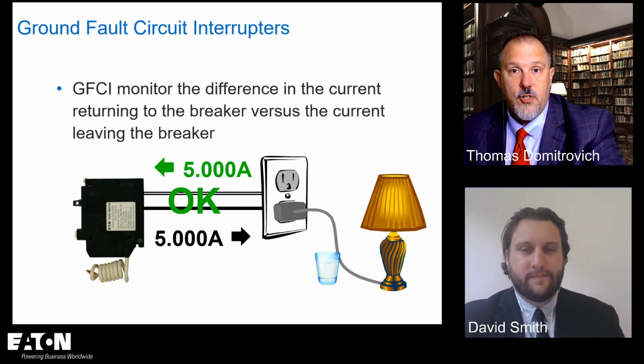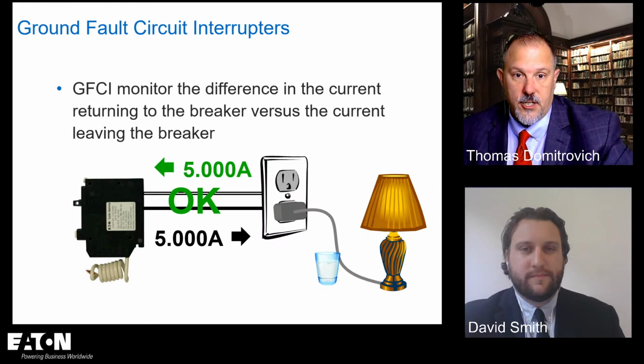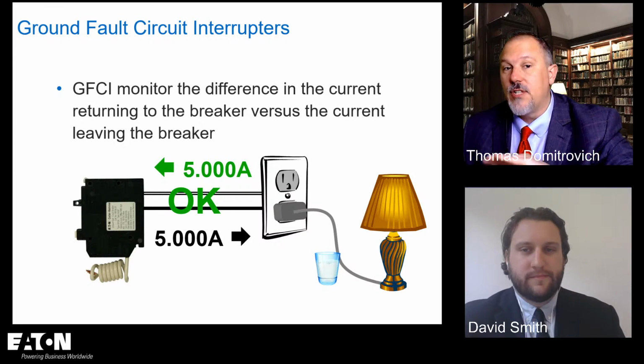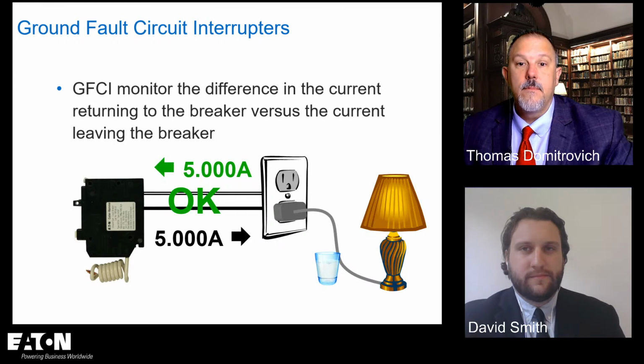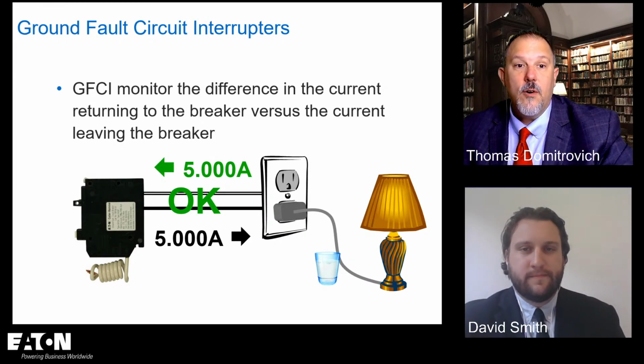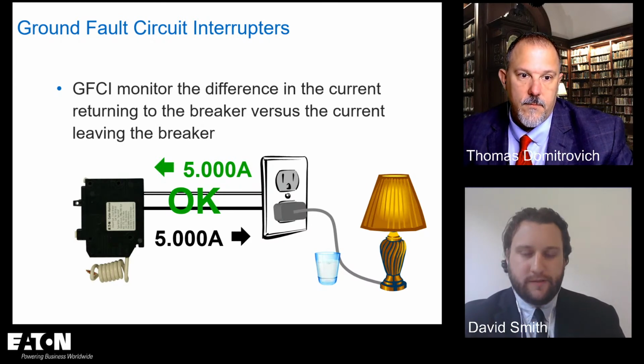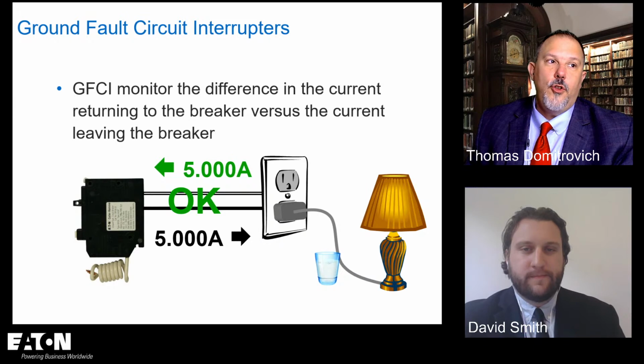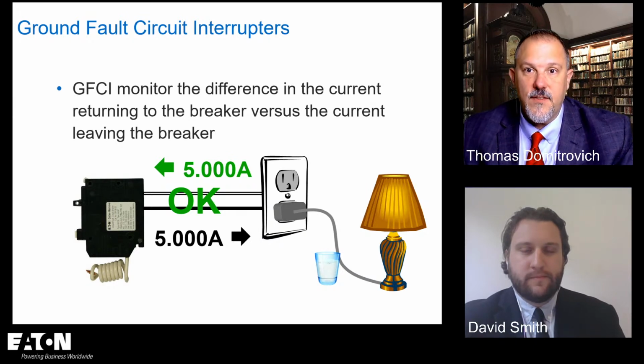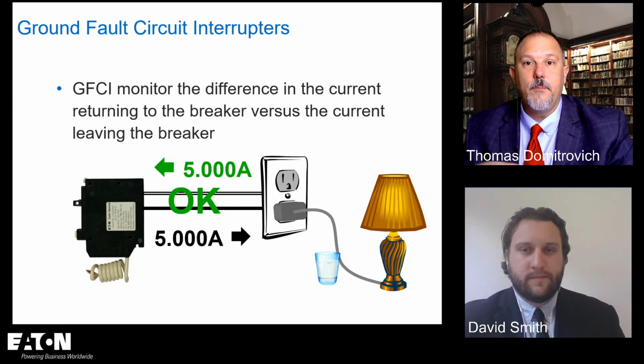GFCI, we covered that on Tuesday. That is shock protection. Any current that goes outside of the path, the GFCI will trip. AFCIs aren't looking for that. They do look at current that goes outside of the path, but they're looking for arcing signatures. That's right. So you can put an AFCI and a GFCI in the same circuit. So there's no compatibility issues.